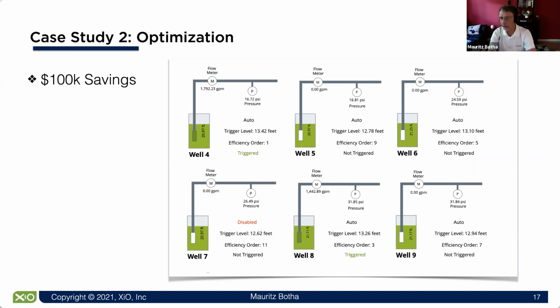So they've got an intermediate reservoir and they pump into that reservoir. What we've started doing is scheduling the pumps based on the most efficient pump, because as the season progresses, the aquifer levels change — I'll show an example of how we monitor that. When those levels change, the pumps become more or less efficient, because they were designed for a specific head, the distance they have to pump water from the aquifer to the surface.